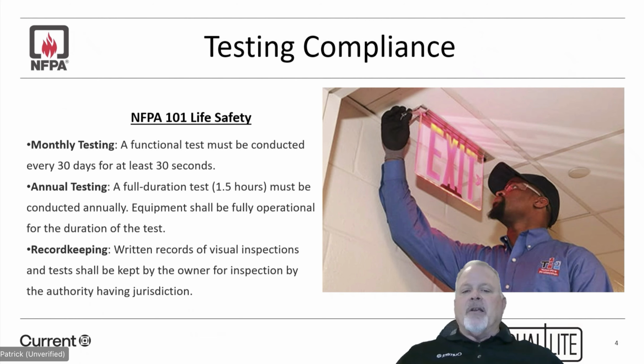Why is this important? Obviously, we have to make sure the product is in working order. But more importantly, as we go through this presentation, you'll notice that these are more decentralized systems versus the inverter, which is a centralized system. We also have to have annual testing, a full duration test, which is 90 minutes. It must be conducted annually, and equipment shall be fully operational for the duration of the test. And then finally, record keeping. Written records of visual inspections and tests shall be kept by the owner for inspection by the authority having jurisdiction, which we also refer to as AHJ.